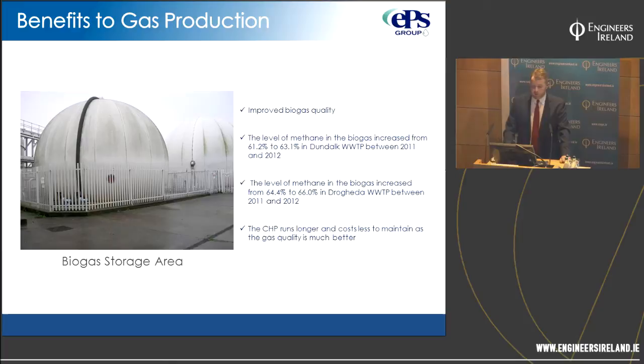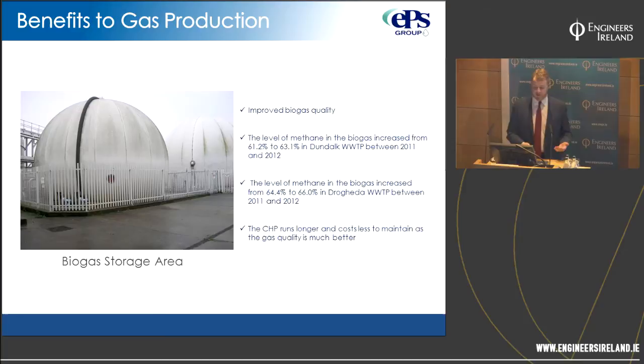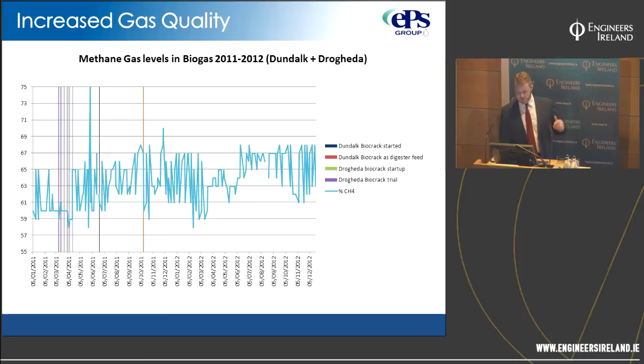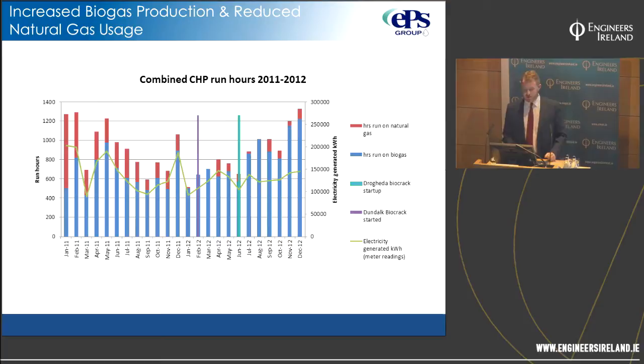One unexpected benefit: due to the conditioning nature of the technology, the level of methane in the biogas increased by between 1.5% and 2%. This is an additional benefit — it reduces maintenance time on the CHPs, because the quality of gas directly impacts maintenance requirements. Looking at the trend data, you can see the average methane quality creeping up since the units came online.